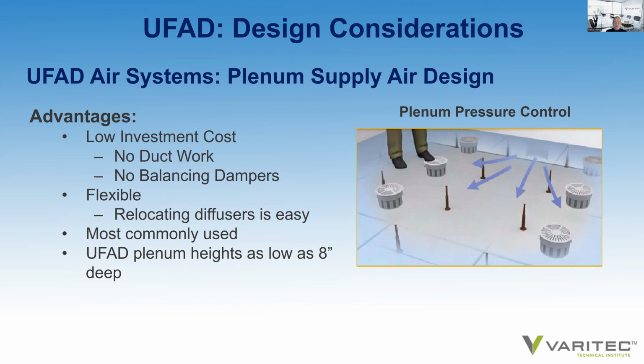No duct work under the floor is required. You don't have a lot of galvanized sheet metal hanging around in your system to be dealing with. No balancing dampers to adjust to make sure air is at the appropriate flow rate at each register and diffuser in order to create the proper flow rates in an environment. Diffuser placement is very flexible, and UFAD plenum heights can now be supplied at 8 inches deep. And I keep mentioning that over and over again because that could mean a lot in a multi-story building in the ability for an architectural design to reduce the floor-to-floor heights in a building.